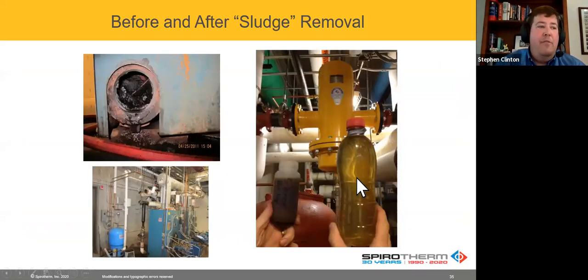This is one that's one of my favorites. This is 75 days it took to clean the system out. Our rep actually had a PO in hand, a good sized PO, to replace all the piping in the entire building. And so they had the opportunity to replace all the piping in the building. And our representative said, no, let's put our unit in, let's clean it up. This was one of the boiler connections. A couple of those other pictures you saw earlier with the completely clogged runouts, that was from this project. We were able to clean that out.